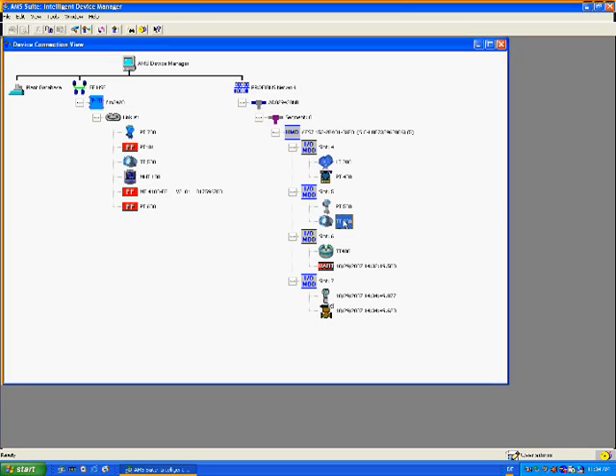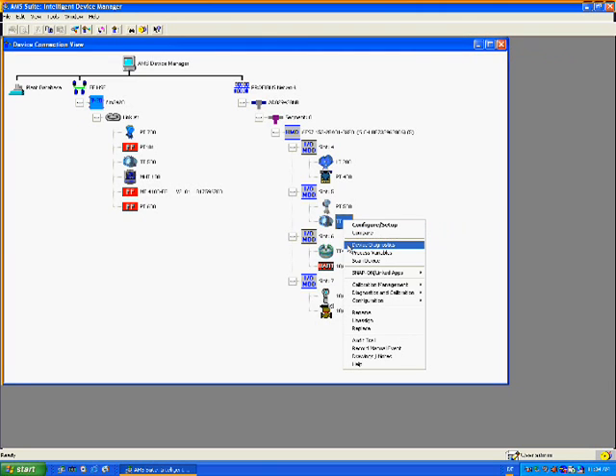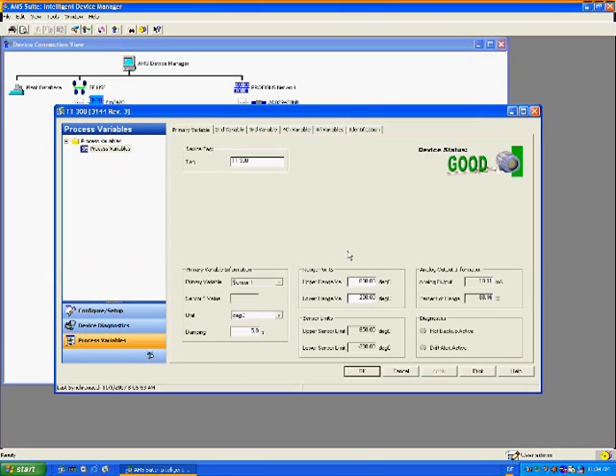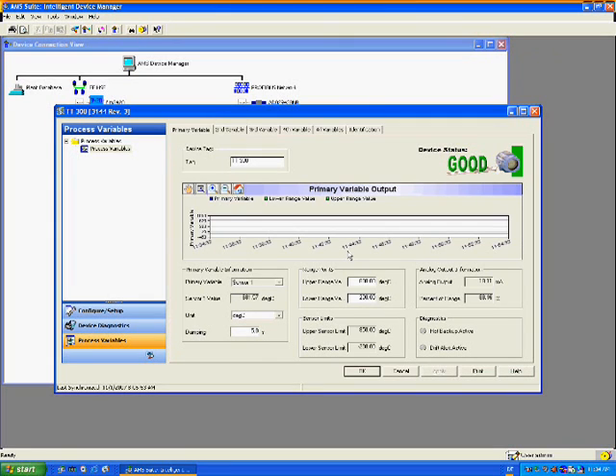In this first system, we click on the device and select process variables from the right-click menu. The display designed by the device manufacturer loads. This device display was designed by the device manufacturer to have six tabs for primary variable, secondary variable, third variable, fourth variable, all variables and identification, as seen on the top of the display. This tab has six frames around the parameters, starting top left with device tag, primary variable information, range points, sensor limits, analog output information, and lastly diagnosis.